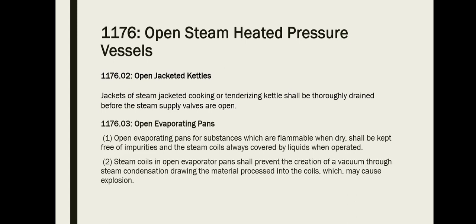Then Rule 1176.03. Open evaporating pans for substances which are flammable when dry shall be kept free of impurities and the steam coils always covered by liquids when operated. Steam coils in open evaporator pans shall prevent the creation of vacuum through steam condensation drawing the material processed into the coils, which may cause explosion.